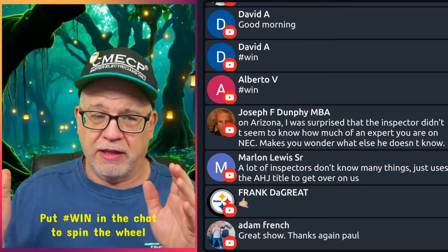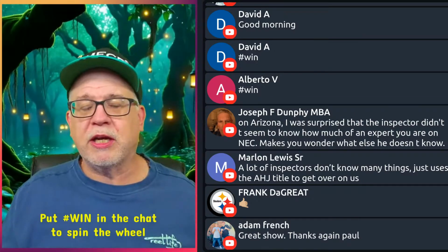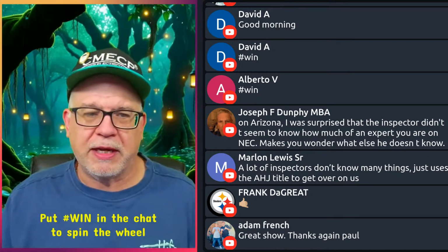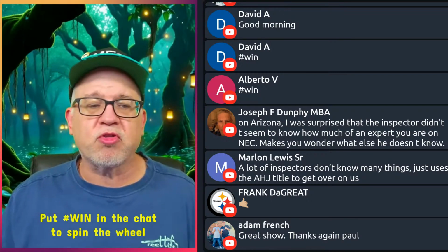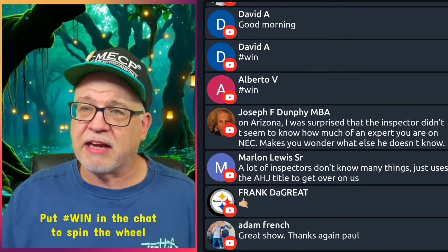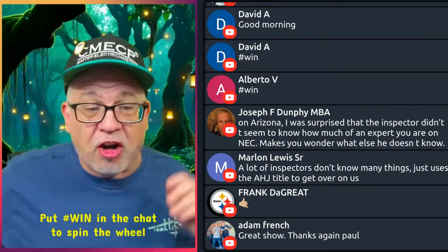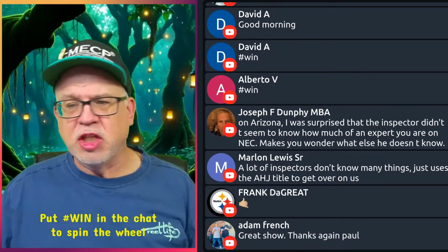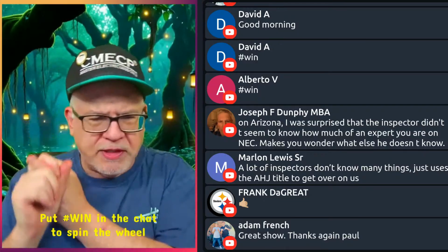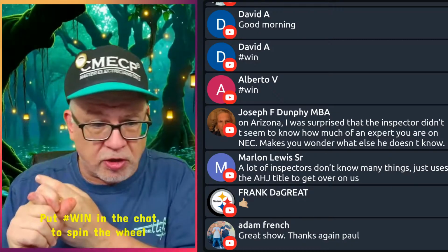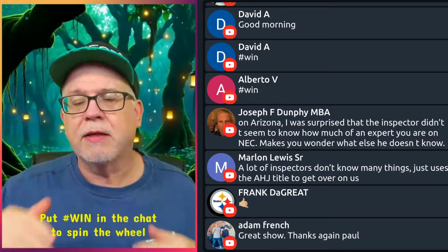And I've done lessons on this. So many people will look at that nameplate. I've seen it all over social media where there'll be something that says minimum 20 amp branch circuit, maximum 40 amp overcurrent device. And people's heads start blowing off because they're like, no, the code says you have to protect the conductor at its ampacity. It's only good for this, and you're going to be protecting it at higher.